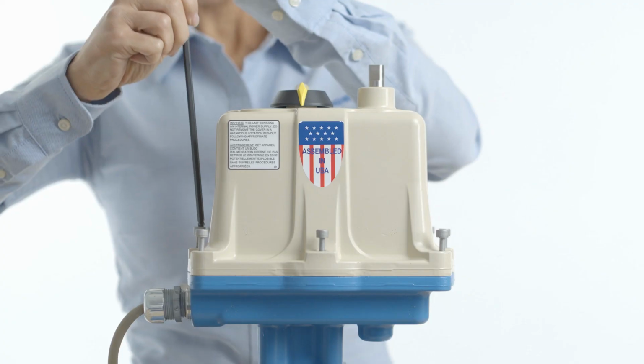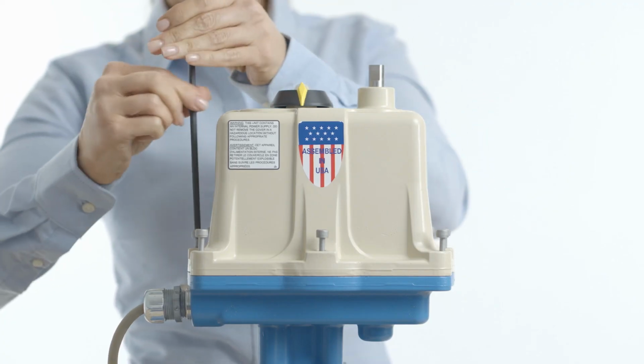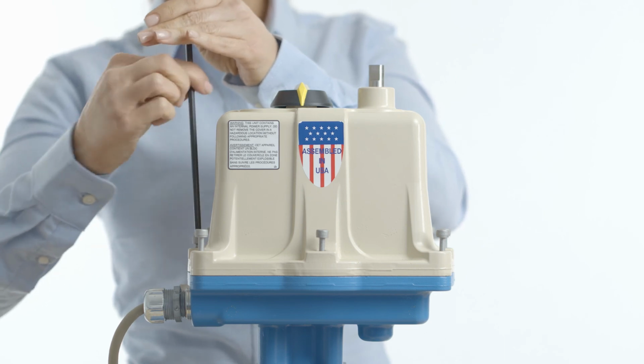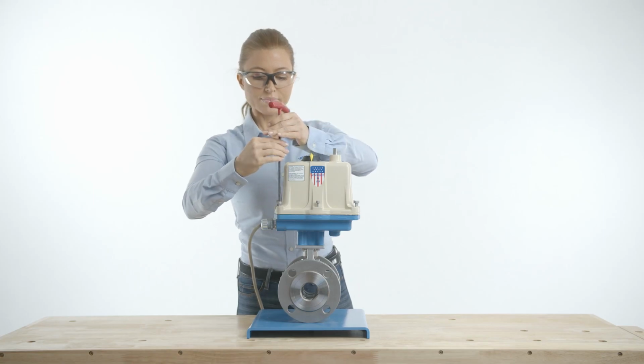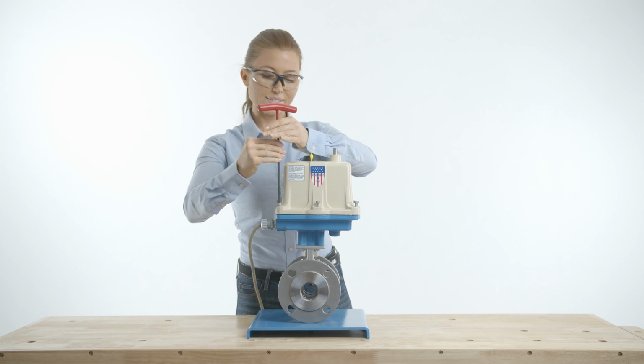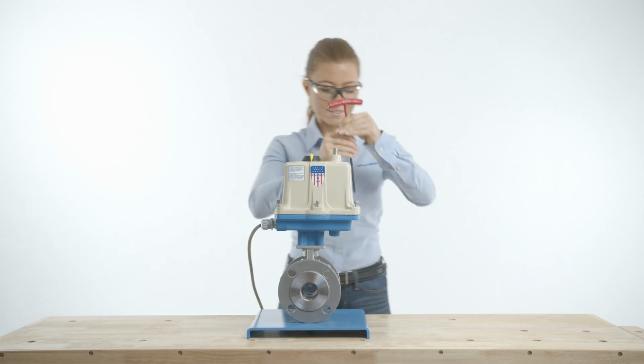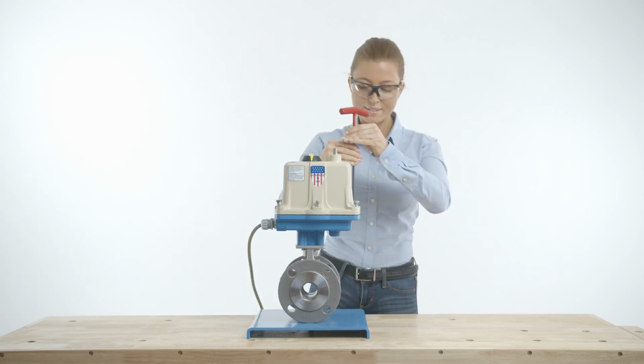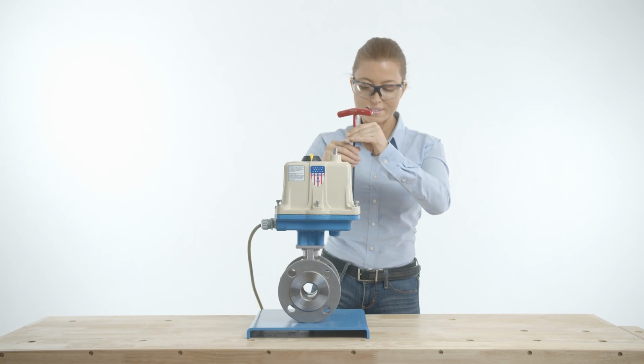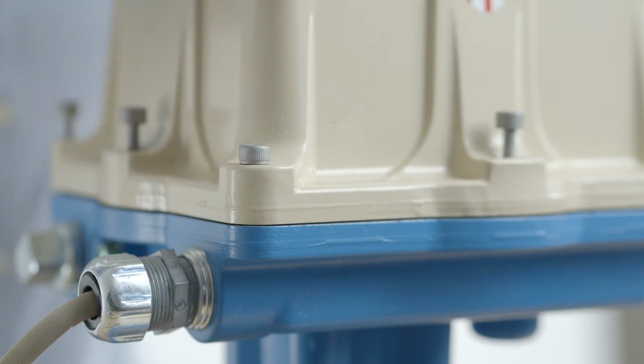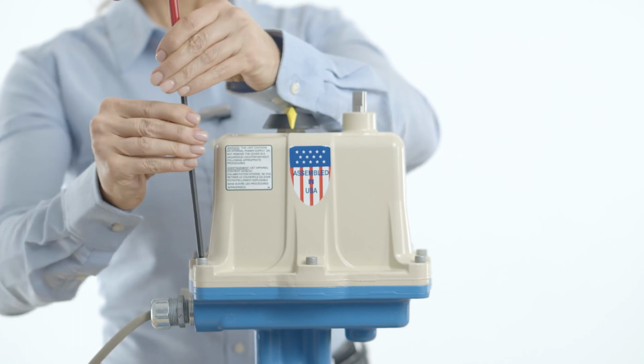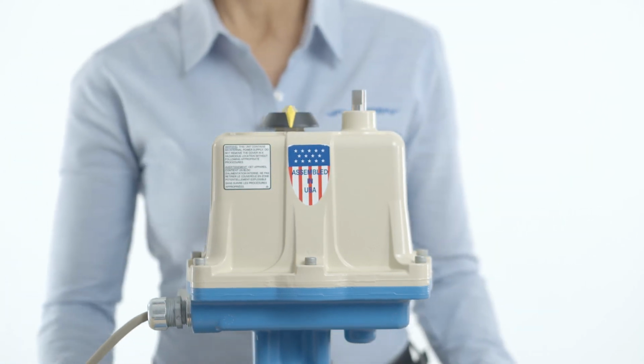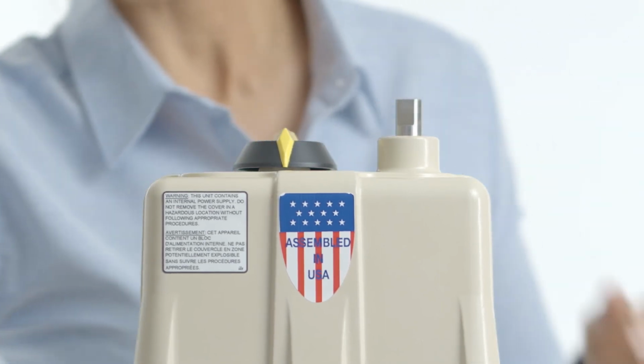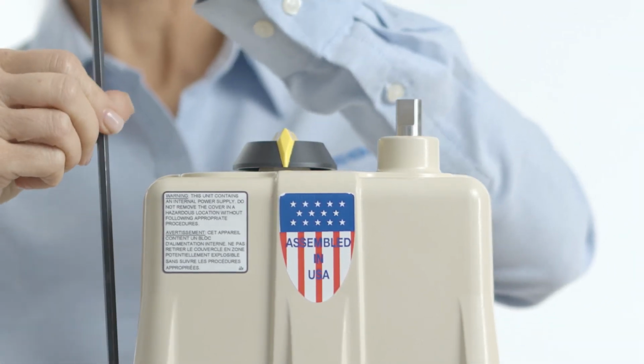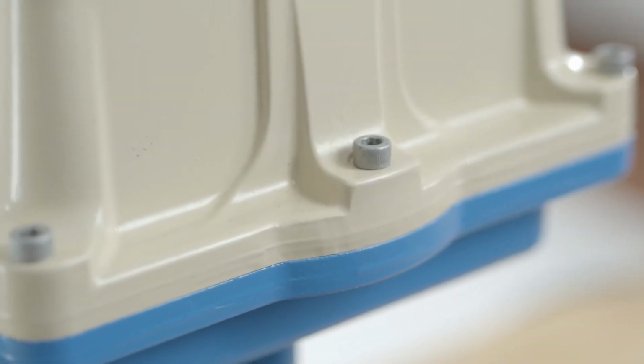Align the cover so the override shaft passes through the override bushing, and carefully push it down so the cover flange contacts the base flange. Once the cover is properly seated, secure the cover by tightening the screws in a cross pattern, which assists with uniform load distribution. If the position indicator is not seated to the output camshaft, turn the indicator until it drops into place. This will ensure accurate visual position indication.